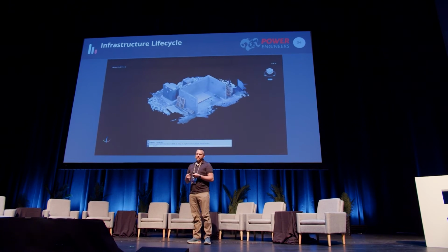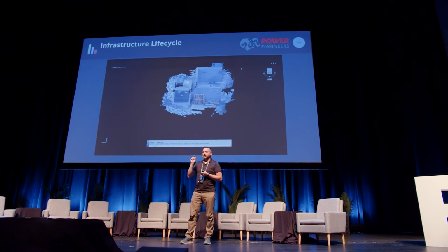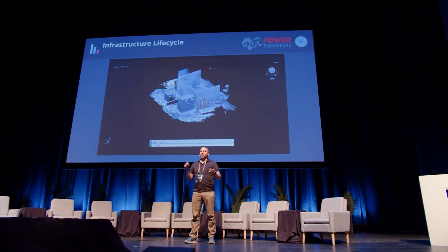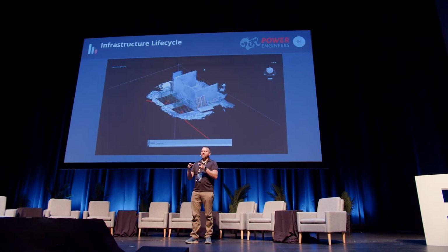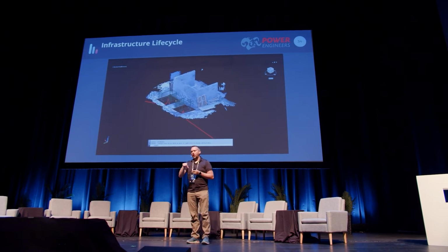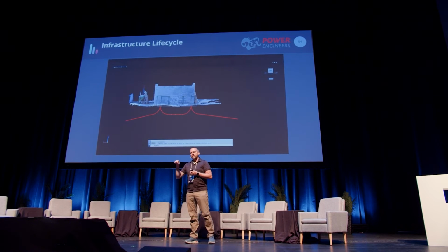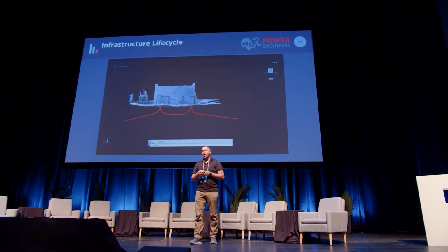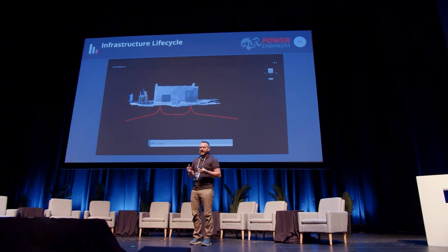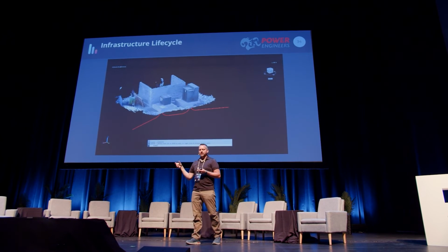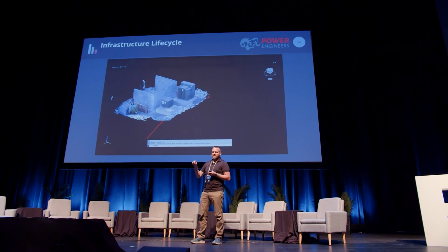A quick example, there was a transformer that we built. This was a small distribution project, and there was controls in place and workflows for review of this process, where on the print, the orientation of one of these electric transformers was shown one way. In the notes, it was specified another way. When it was installed facing this block wall that you see on here, they had to rotate that transformer, come back and change it. It was a small change, but the review process missed it.